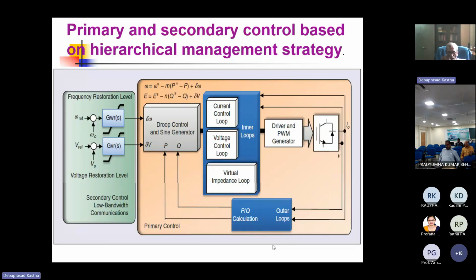So what does the primary control do? It basically sets the voltage and frequency of the AC bus of the microgrid. So the current control loop, voltage control loop, and virtual impedance control loop are actually the job of the local controllers, which is done with the local control. Generally, this is done using droop control. So usually there will be some variation in the voltage level and the frequency level, which needs to be restored by the secondary control.